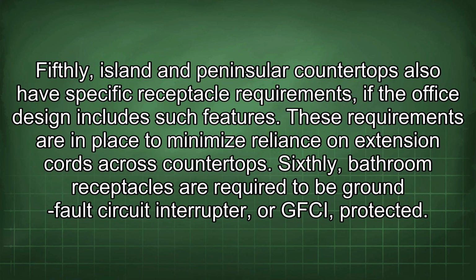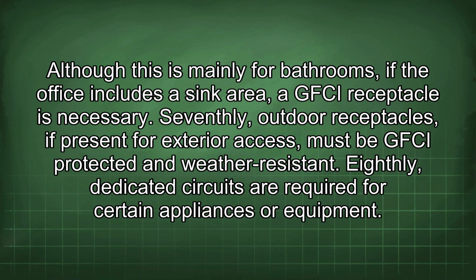Fifthly, island and peninsular countertops also have specific receptacle requirements, if the office design includes such features. These requirements are in place to minimize reliance on extension cords across countertops. Sixthly, bathroom receptacles are required to be ground fault circuit interrupter, or GFCI, protected. Although this is mainly for bathrooms, if the office includes a sink area, a GFCI receptacle is necessary. Seventhly, outdoor receptacles, if present for exterior access, must be GFCI protected and weather resistant.